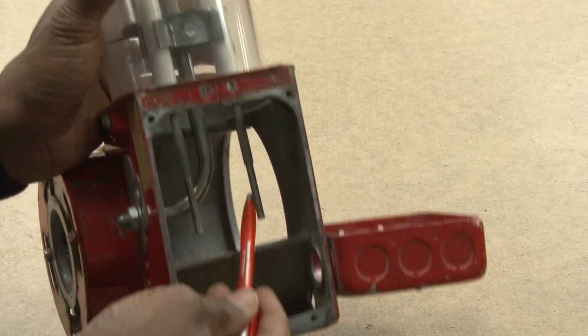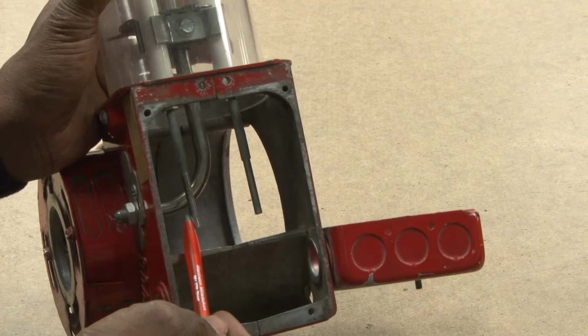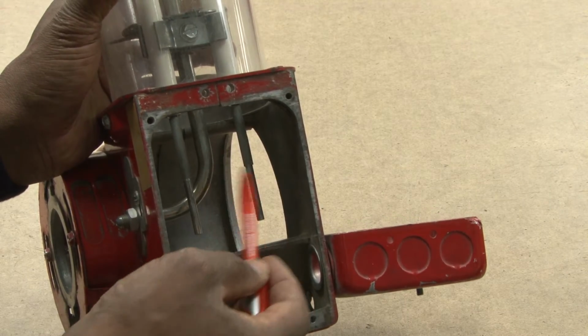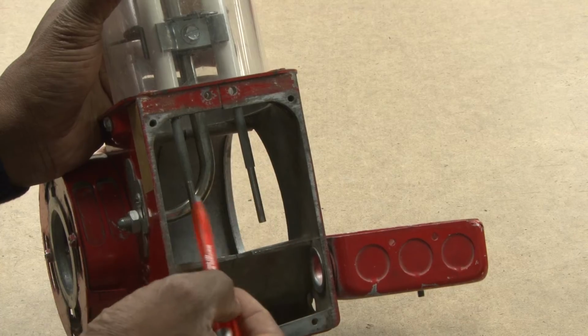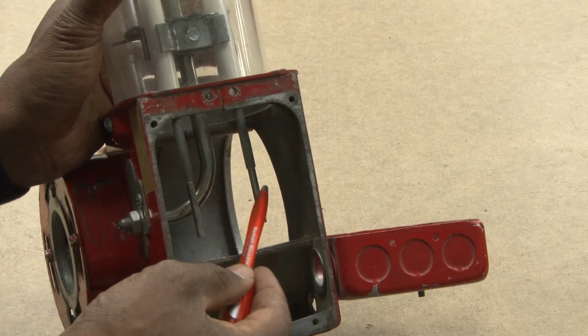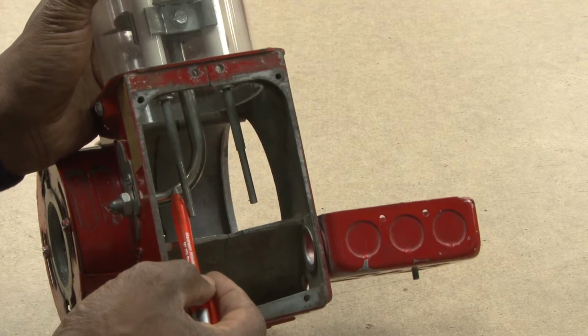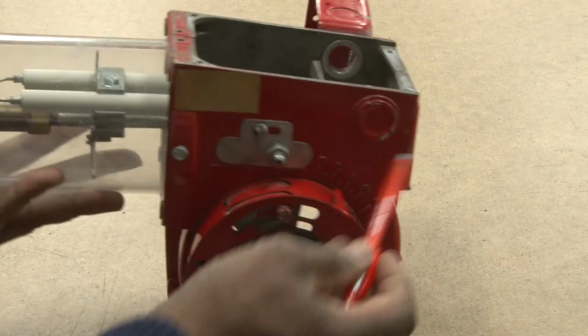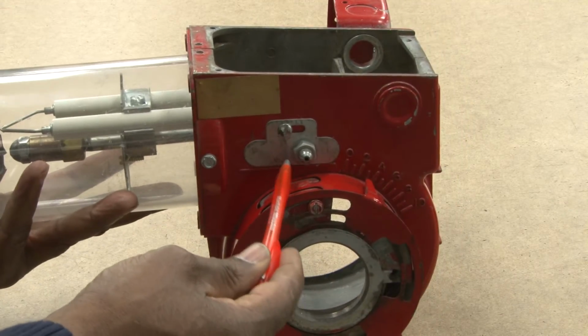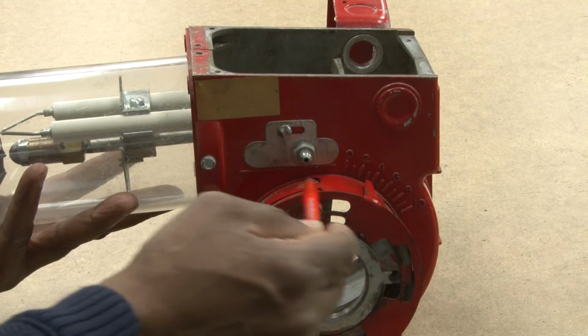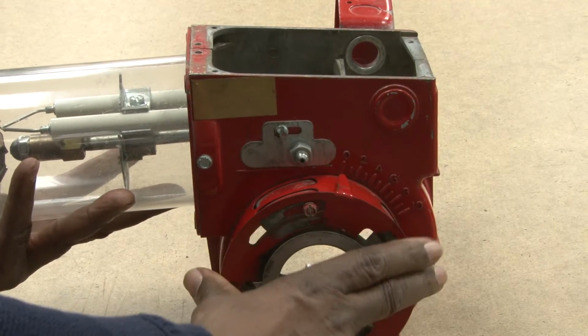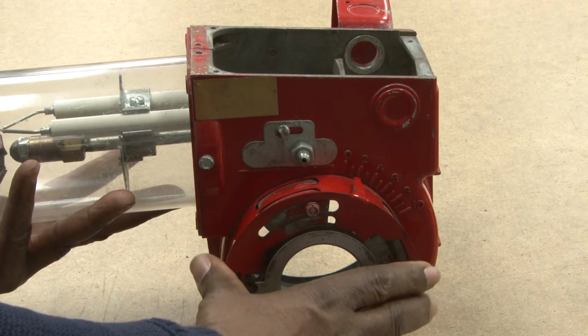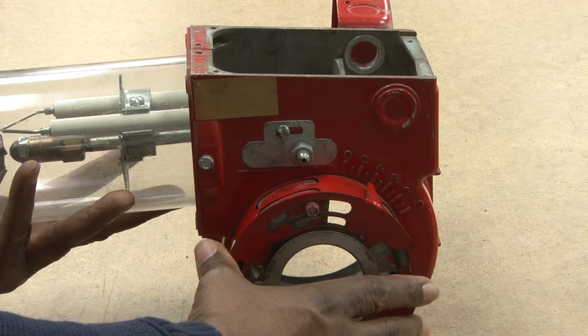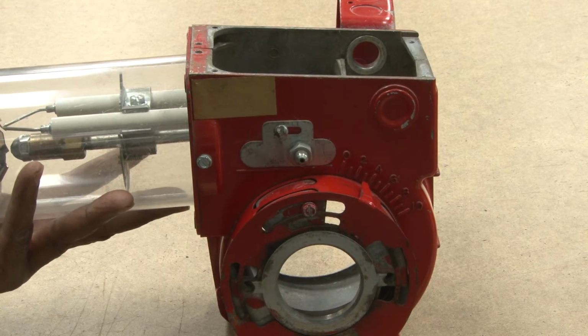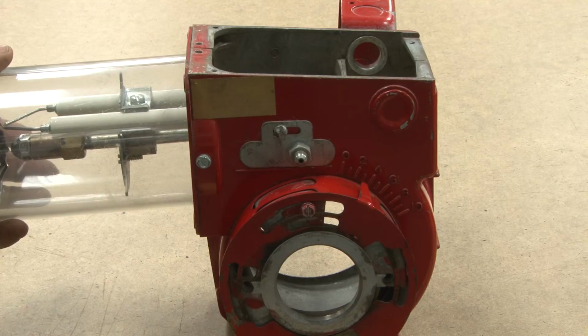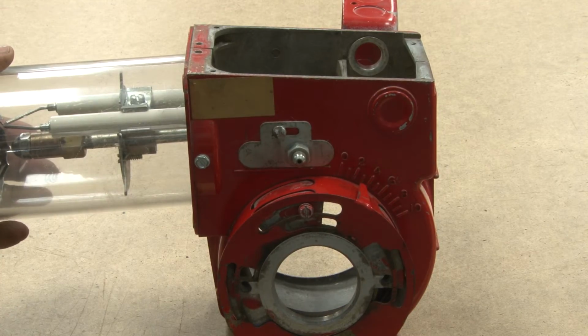These are the electrodes coming down, where the transformer would sit on top of this to rest those two springs from the transformer to make contact to the two probes. The oil will come in on the side. The air shutter is here, where we will adjust the air shutter by moving this, then putting a set screw to lock it in place. Once it's properly adjusted, it's set for good. There's no need to readjust it each year.